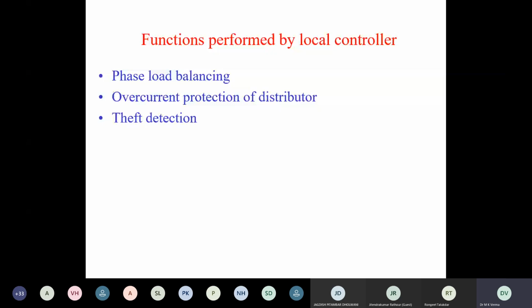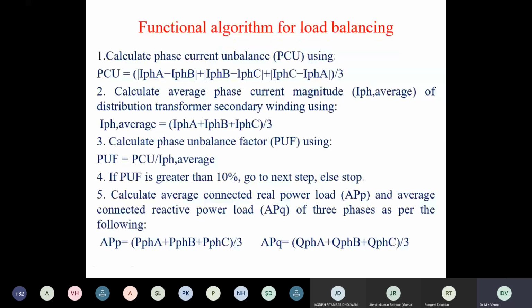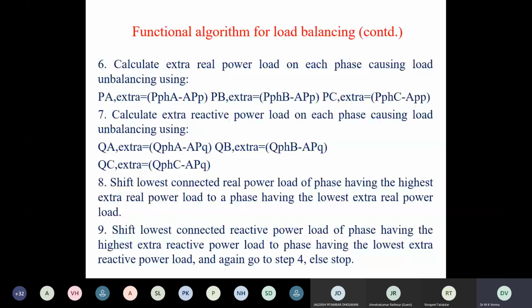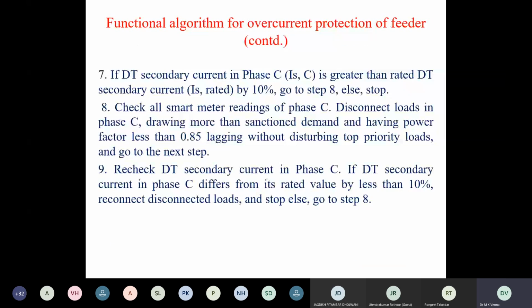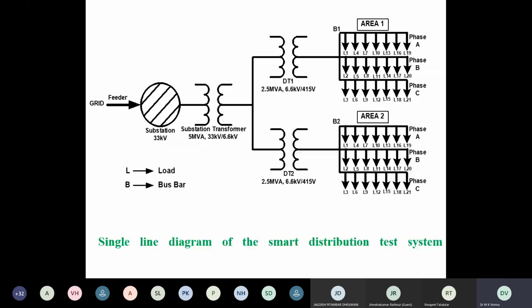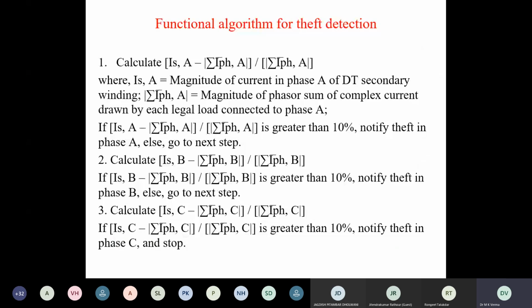These are functions performed by the local controller. The local controller does phase load balancing, and it detects overcurrent in certain feeders and eliminates the overcurrent. It also detects thefts, etc. So these are algorithms developed for load balancing, and this one is for theft detection. It also considers simultaneous occurrence of different events like load unbalancing, power theft, and overcurrent.